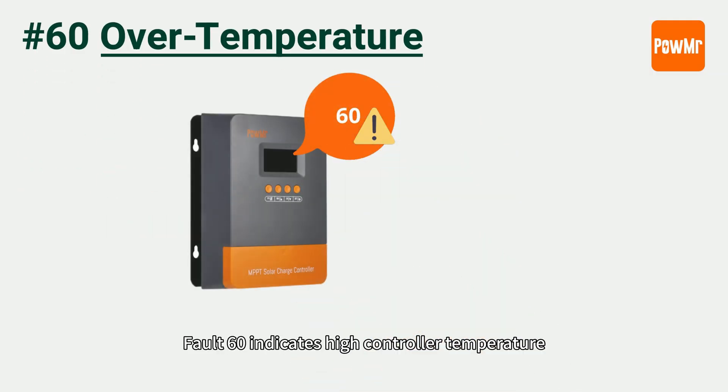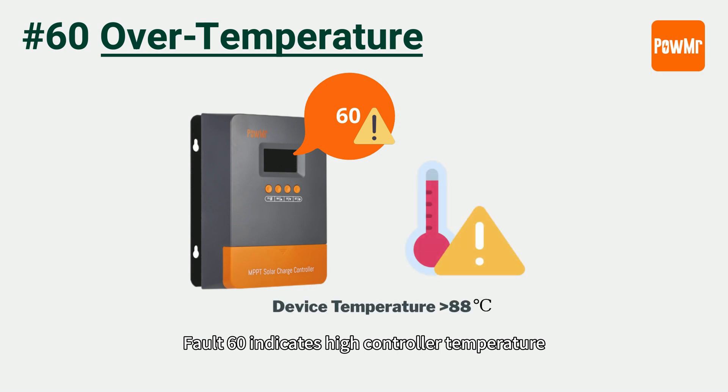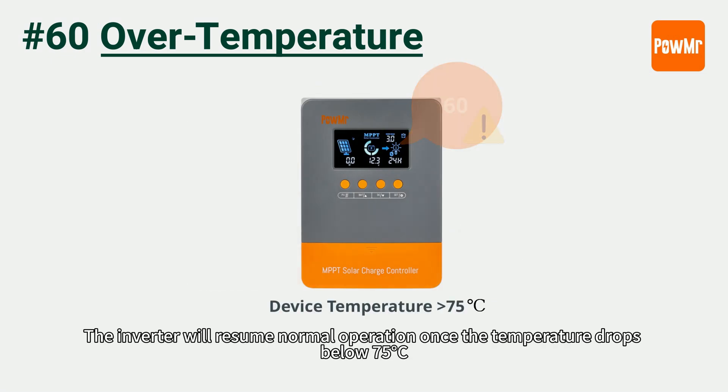Fault 60 indicates high controller temperature. When the controller temperature exceeds 88 degrees Celsius, it will automatically stop charging and discharging. The controller will resume normal operation once the temperature drops below 75 degrees Celsius.